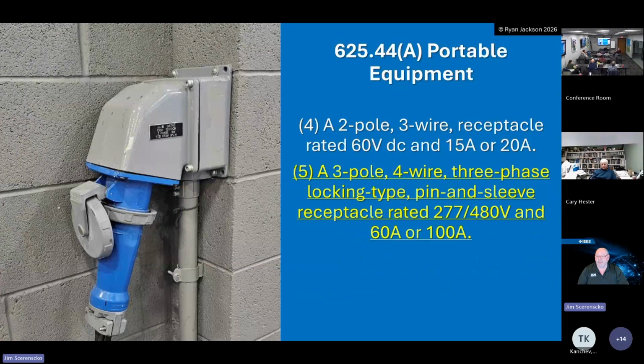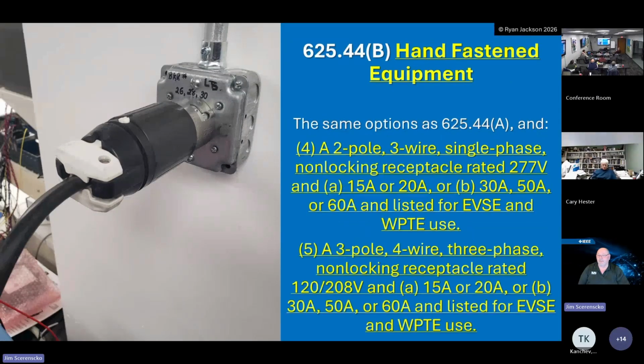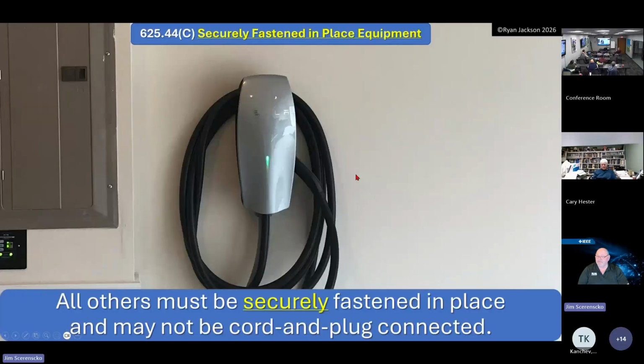And then also portable equipment. Number 5 was added, a 3-pole, 4-wire, 3-phase locking type pin and sleeve receptacle rated 277/480 volts and 60 amps or 100 amps. Hand fastened equipment: there was a definition put in for hand fastened equipment and what it means. If you go back and look into definitions, securely fastened means it can stay on the wall, and I don't think you can just lift it off and take it with you. Hand fastened means you hang it on the wall while it's charging, and you can just pick it up and remove it, put it in the trunk or the hatchback, and take it with you.